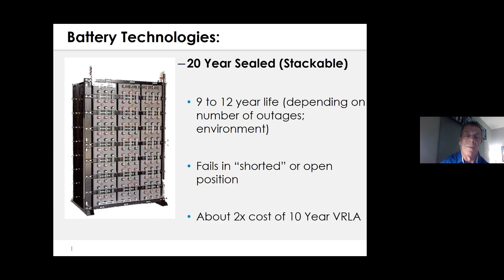One of these, the 20-year batteries, they fail on the front. So you can see along the front of the unit, where'd my mouse go? There we go. On the front of the unit here is where it's indicated to a technician where the failure is. You can see right there that when a unit goes, as opposed to the 10-year batteries, it's typically located on the top, so you have to pull out the individual strings and take a look at them. A little bit of extra work to take them out. Here, they're a little bit easier to see.